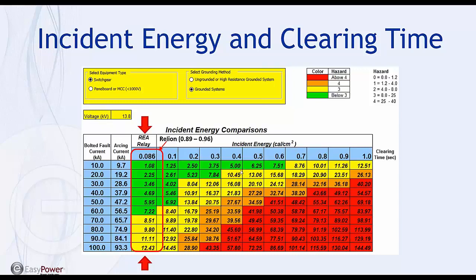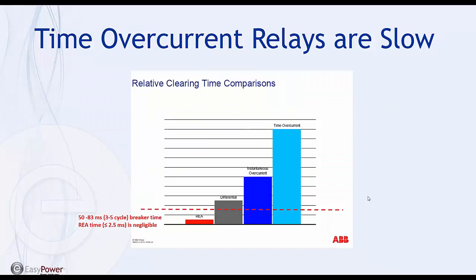So you can see here in the green, that's below hazard category level 3, and so it takes quite a bit of fault current before you start getting into the higher danger zones. And you can see here also that it depends on the grounding and the equipment type. So ultimately, though, you're looking at speed. That's really the main driver. And so if you don't have an arc flash system, whether it's dedicated or built into a relay, then there's definitely a risk. Time over current relays are too slow.